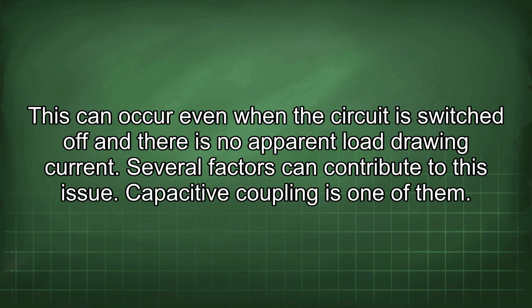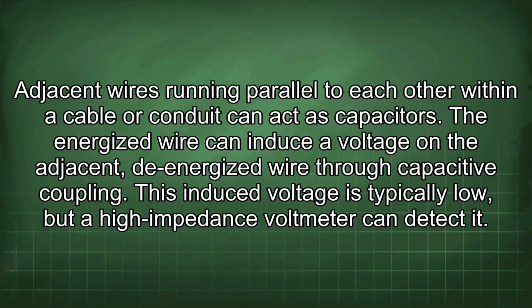Capacitive coupling is one of them. Adjacent wires running parallel to each other within a cable or conduit can act as capacitors. The energized wire can induce a voltage on the adjacent de-energized wire through capacitive coupling. This induced voltage is typically low, but a high impedance voltmeter can detect it.